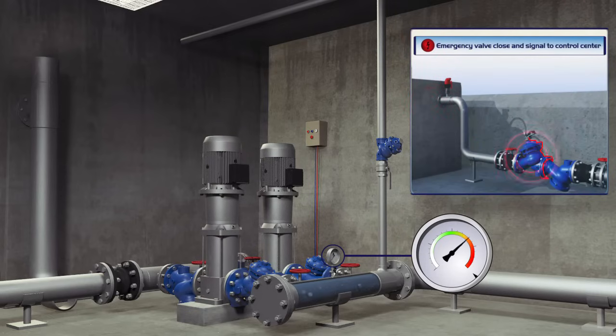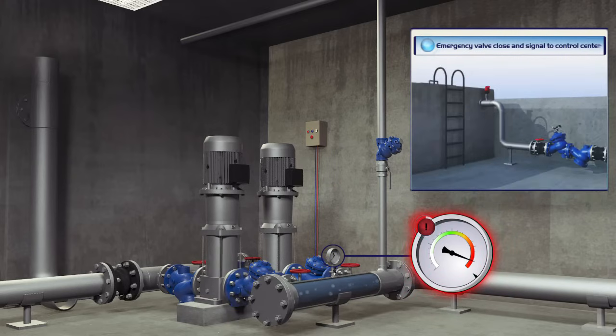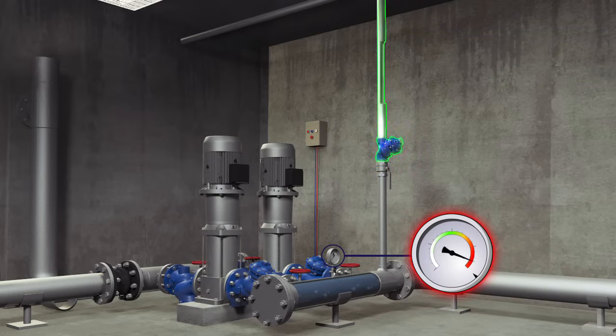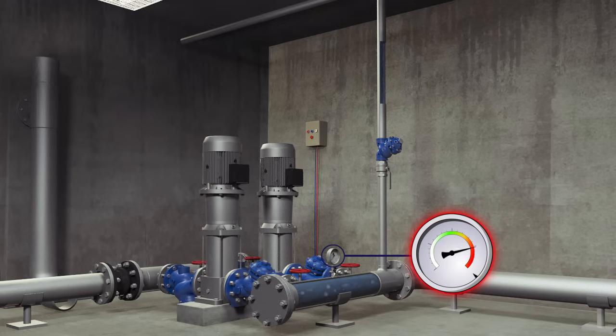If the lift pump would continue to run, the pressure in the supply line of the rooftop reservoir would rise to a dangerous level that could damage the system. To avoid this happening, the Bermad system includes a pressure relief valve located at the pump outlet in the basement. The valve releases excess pressure back to the lower reservoir, thereby protecting the system.